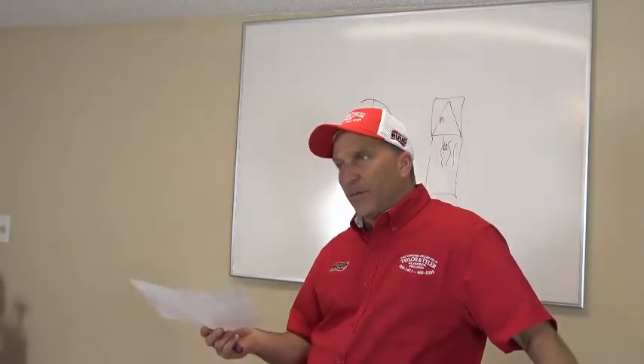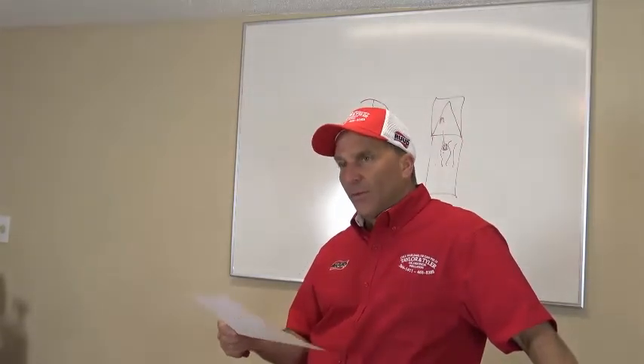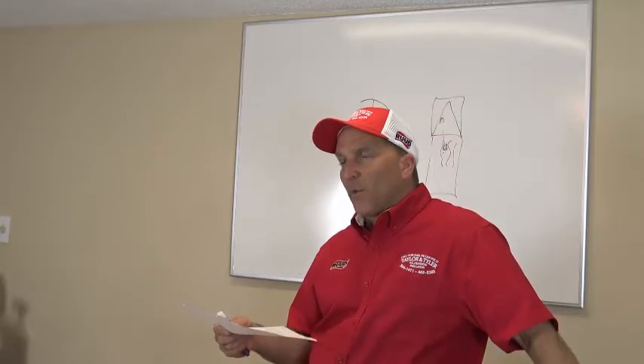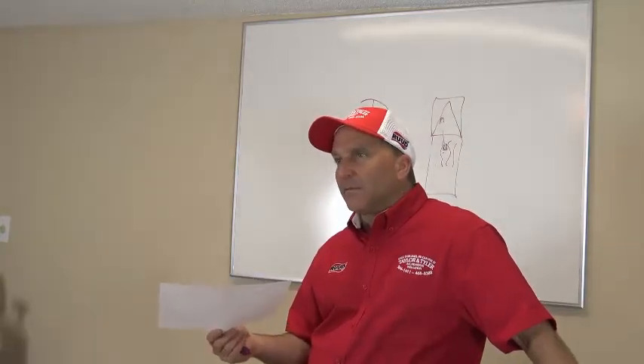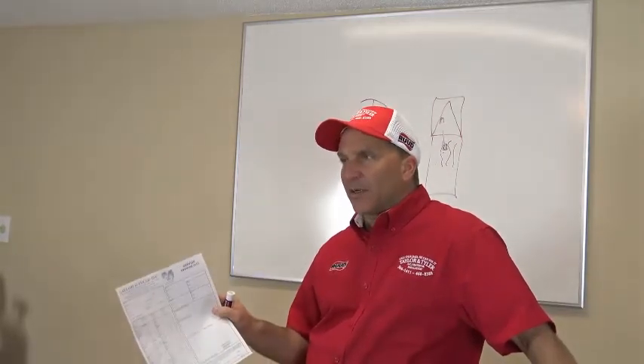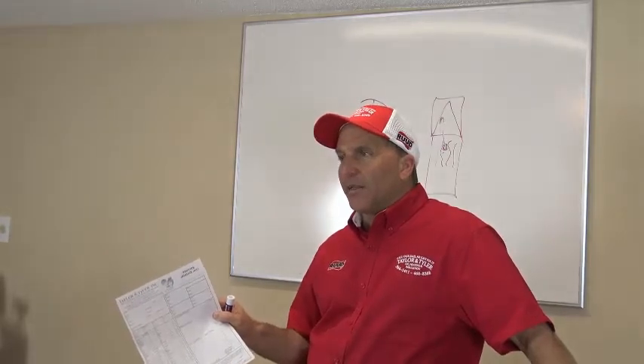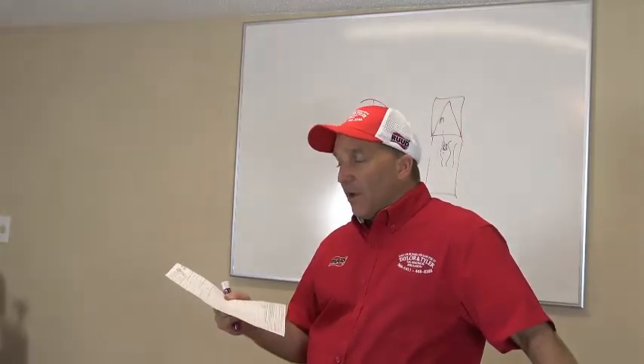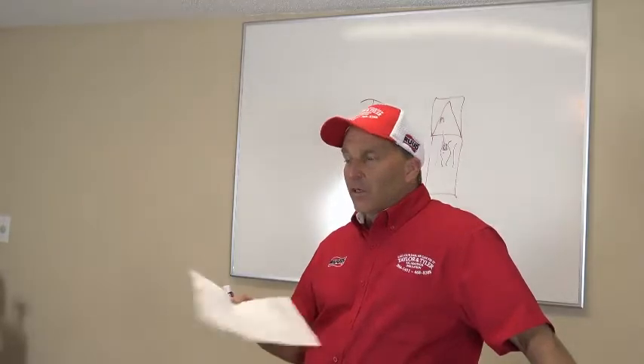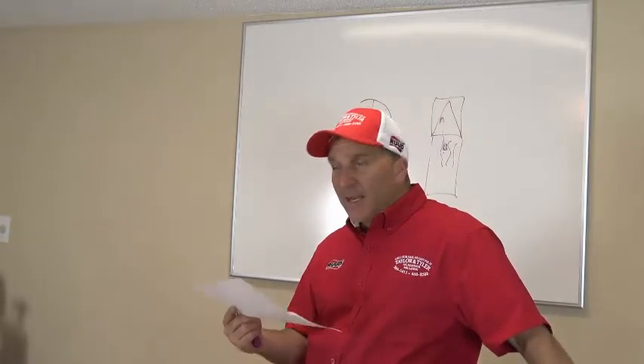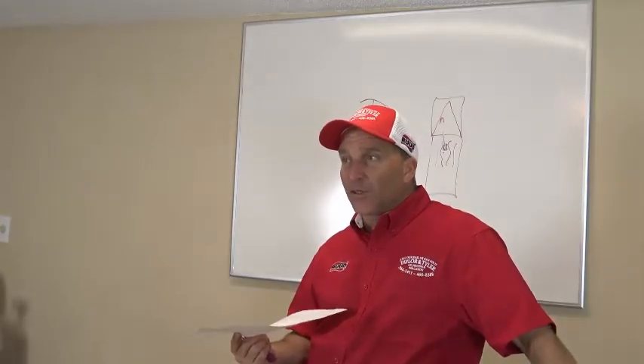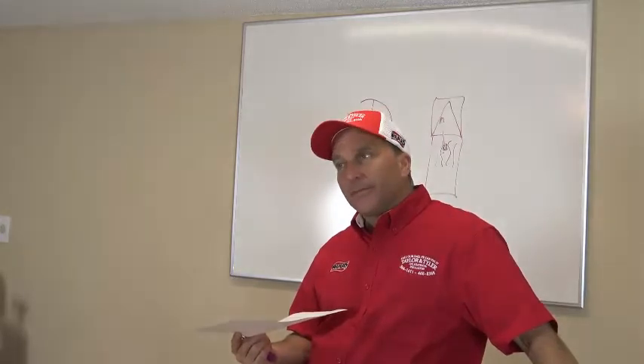And I go, yes ma'am, you should, because refrigerant has no warranty. Well, your guy didn't fix the leak. Well, you didn't pay for the leak fix. Well, he didn't tell me where the leak was at. Well, you didn't pay for him to do a leak search. Oh, wait a minute. He didn't even recommend that we do a leak search. Now whose fault is it?